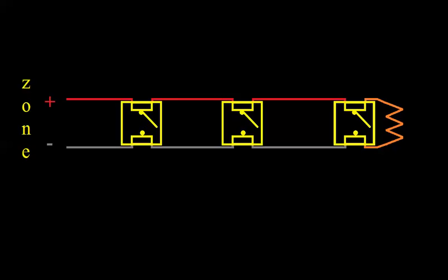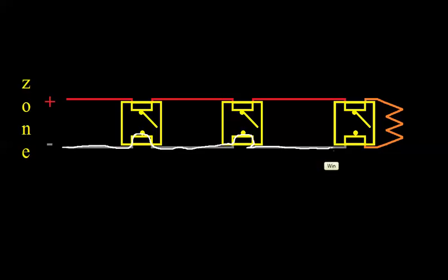We've gone over this a few times. This is a conventional zone, and we know that they use current monitoring to detect either complete circuits, open circuits, or alarms. They do that by using an end-line resistor that limits the current on the circuit. We have a certain amount of voltage, usually around 24, at the front of the zone. Then we have all our normally open devices, and at the end we have this resistor. The current can't go through any of the devices because they're normally open, so it flows through this resistor, which limits how much current can flow. The panel detects that as a complete circuit.